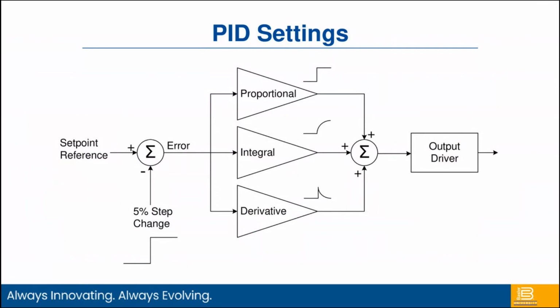We go back to our block diagram. This is calculating that error signal. So I've got my set point change and I've got my error signal, and now I'm taking that error signal and I'm multiplying it times each one of those gains to create the output that's going to drive my power stage.